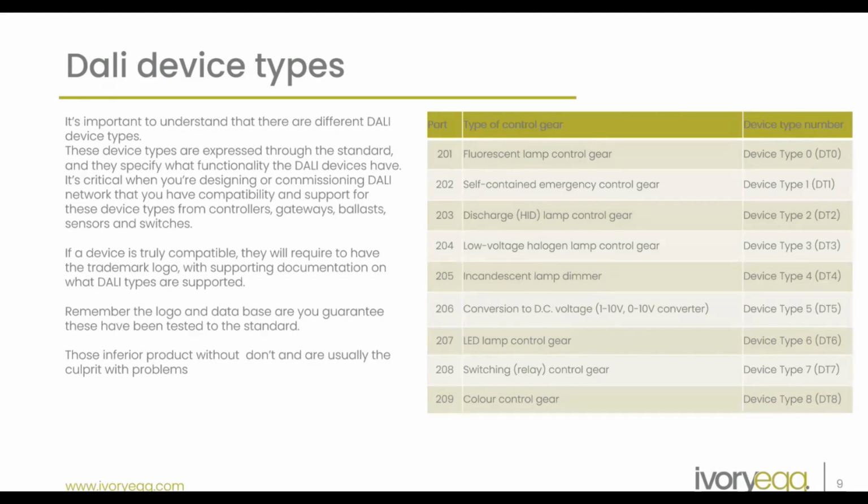I see this time and time again. People coming to us, I can guarantee you every product we sell is Dali certified. We just don't run the risk. And every time, it doesn't matter whether it's us or someone else's gateway, I see inferior fittings that are usually bought much cheaper that don't have the logo, or they've had the logo falsely put on them and they're not available in a database. And then there's usually problems with them.